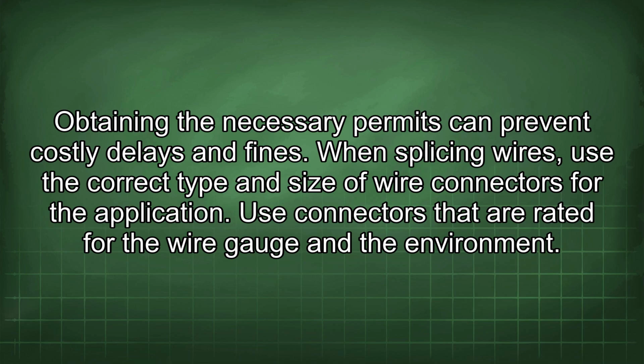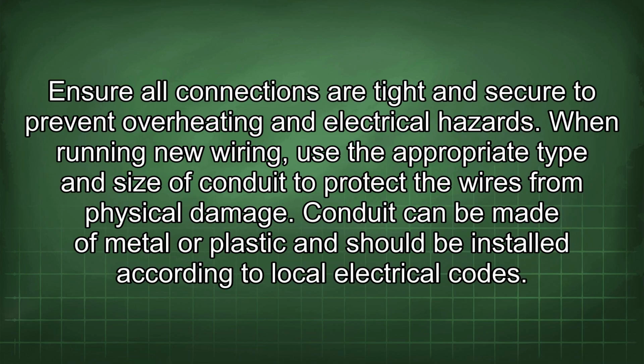When splicing wires, use the correct type and size of wire connectors for the application. Use connectors that are rated for the wire gauge and the environment. Ensure all connections are tight and secure to prevent overheating and electrical hazards. When running new wiring, use the appropriate type and size of conduit to protect the wires from physical damage. Conduit can be made of metal or plastic and should be installed according to local electrical codes.